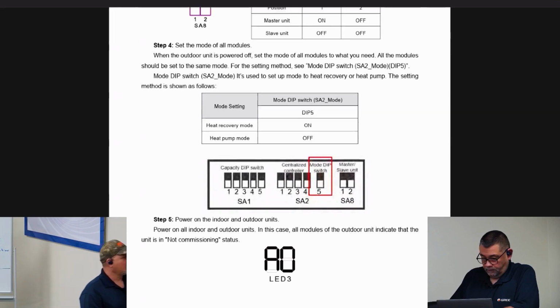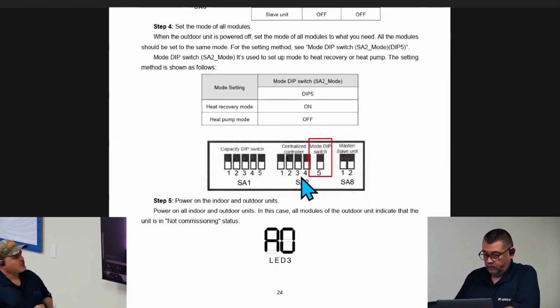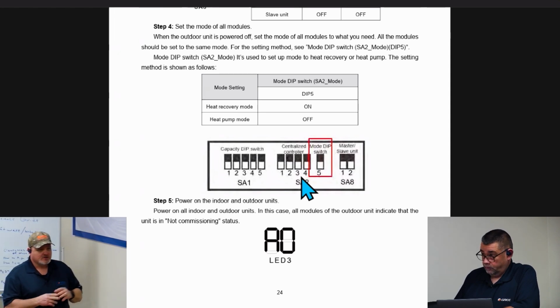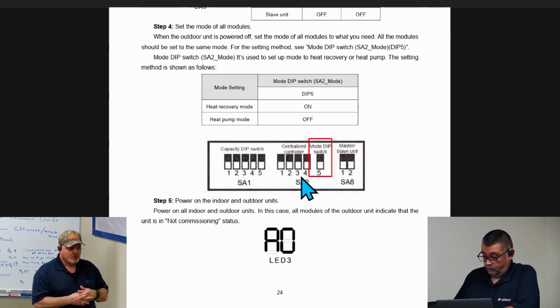Right. And that comes back to what we talked about as far as central control or cool automation, when you're setting the dip switches, which I believe is SA2. Yep, it's right here. You move your little highlighter over to SA2, your mouse. SA2 dip switches are right there, those are for central control. So once you have a master and a slave unit piped together, that becomes a system. And if you have another master and slave, that's another system. So you've got system 1, system 2, system 3.